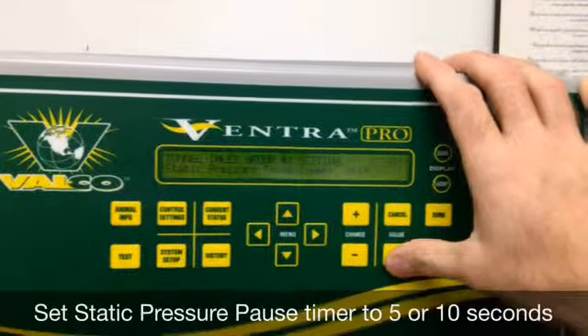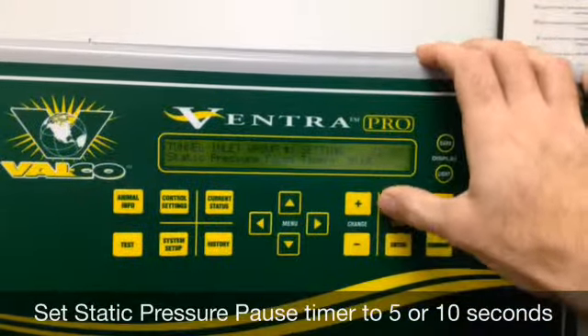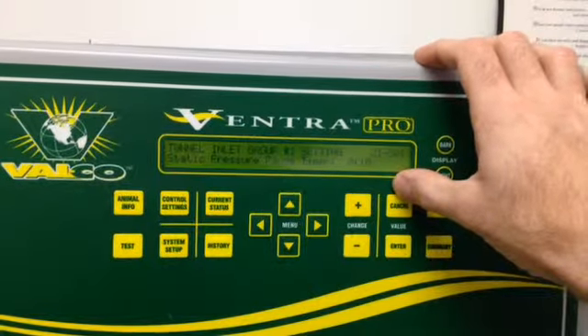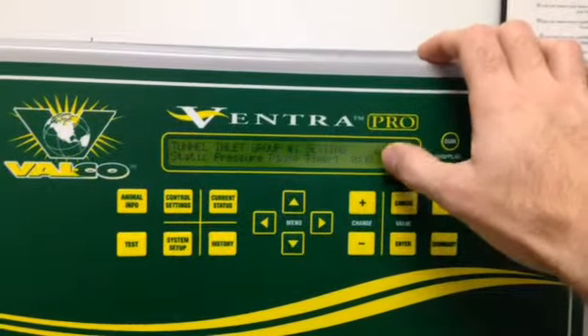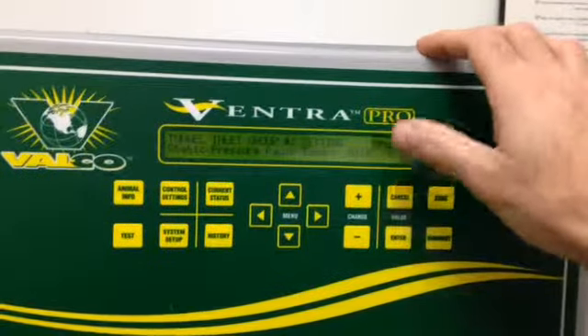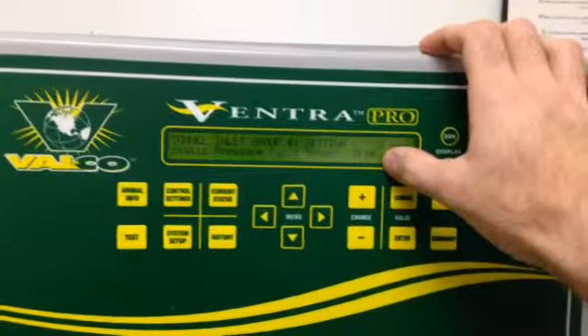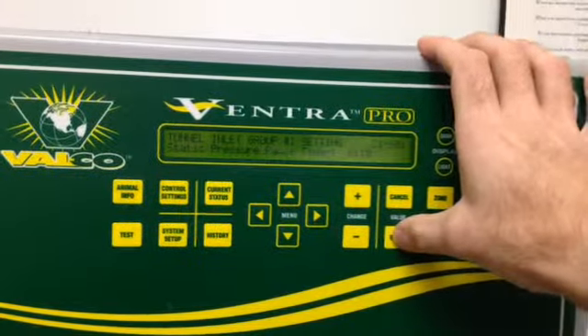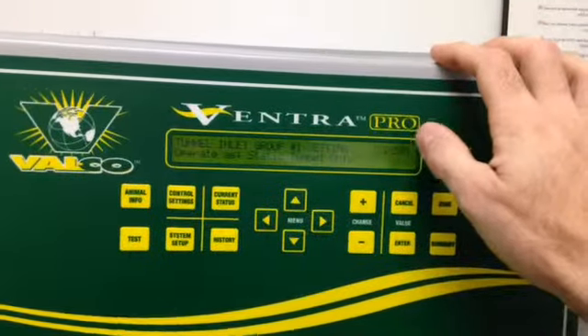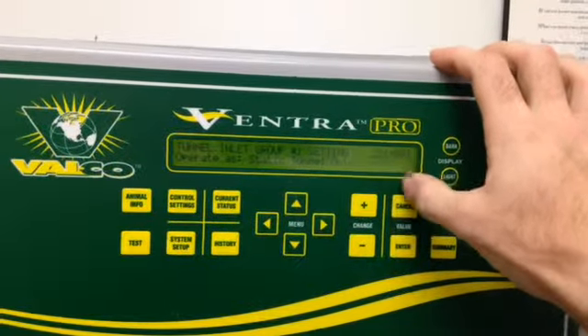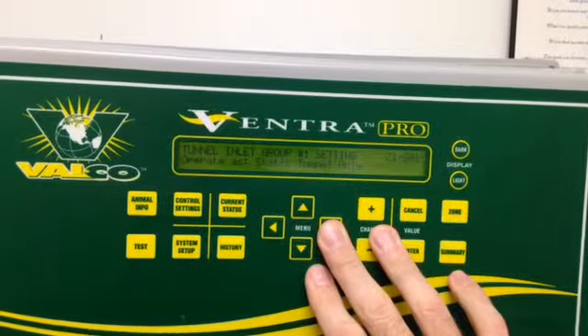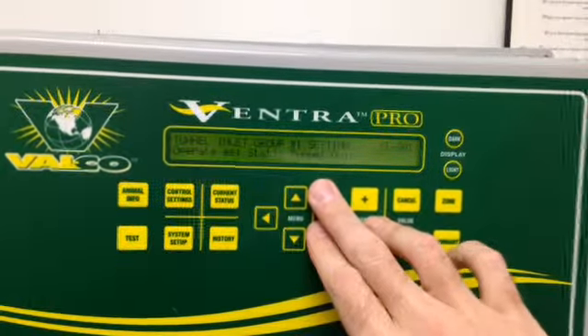This simply says how long after moving the curtain is it going to wait before taking a static pressure reading. This eliminates things from gusts or breezes causing the curtain to move up and down regularly. Somewhere between 5 and 10 seconds is usually a good number to start from. After that, we're back to the beginning of static tunnel only, so that completes all of the settings we need to do for the tunnel inlet group number 1 itself.